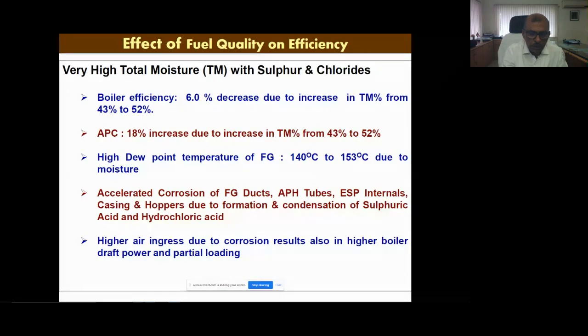Now, as I already discussed, there is a moisture issue. So our focus is on how to reduce the moisture effect on the efficiency and the overall performance. If we go by the data, boiler efficiency is decreasing by 6%, mainly because of the increase in moisture in the lignite from 43% earlier to 52%. As I explained earlier, just a 1% drop costs us around 5 to 6 crores. So for 6%, it is in the range of 25 to 30 crores. That is the impact of this increase in moisture.